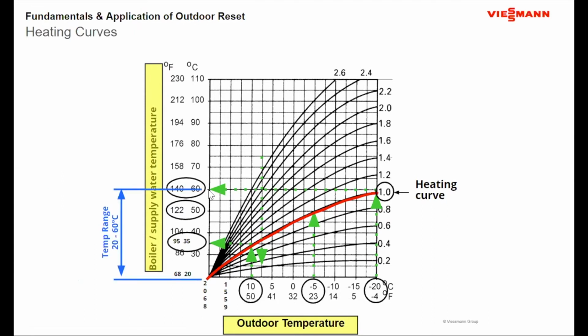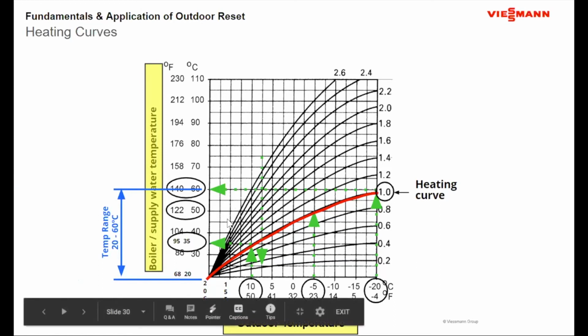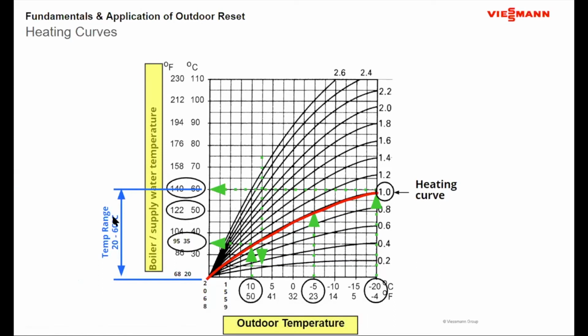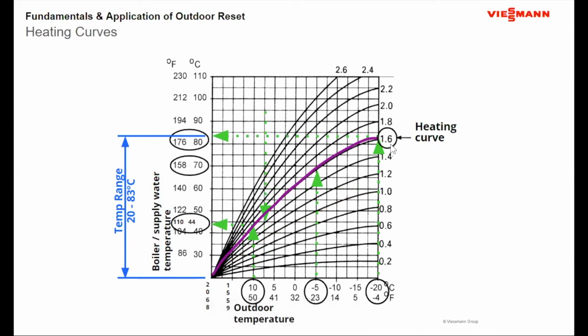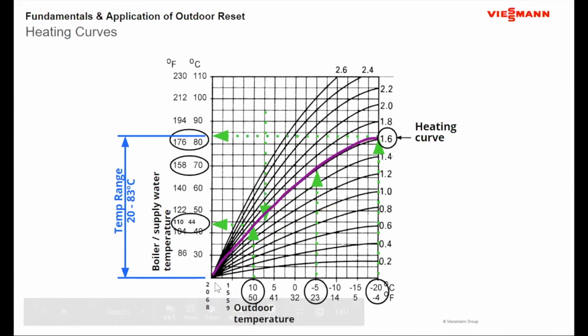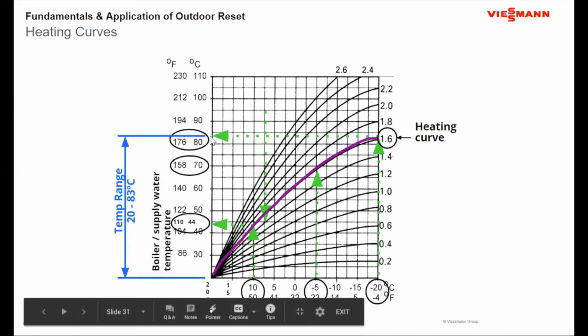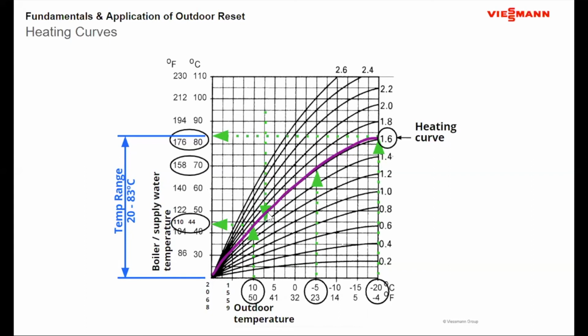And what will happen is each building, depending on the design condition, will have a temperature range. So here it's in Celsius, so anywhere from 20 degrees Celsius to 60, or 68 degrees Fahrenheit to 140 Fahrenheit. The water temperature can vary based on outside temperature. If I have an application that has baseboard, I'm looking for water in the range of about 180 degrees. So my heating curve is more of a 1.6, -4-degree day, 180-degree water. Now the temperature range goes from 68 degrees up to 180 degrees. And it's all about making sure that this becomes the right combination to heat that building.